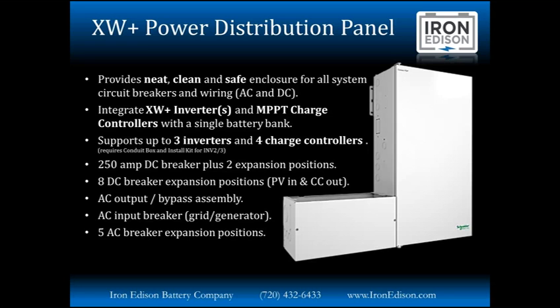What we typically do there is put all of the charge controller output breakers in the power distribution panel, and we'll relocate the PV input breakers to a separate box on the wall adjacent to the power distribution panel. This also includes the AC output and bypass assembly I just described, and it has all the input breakers for both the AC1 and AC2 inputs, and 5 additional AC breaker expansion positions. If you're doing all 3 inverters, those will get occupied by the additional output bypass assemblies as well.